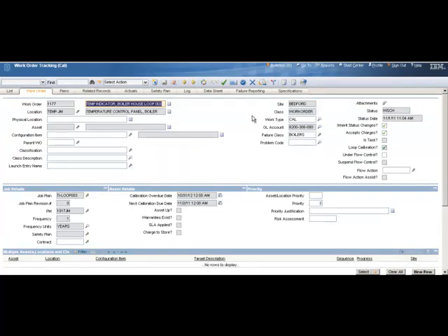I forced it to generate a calibration work order, and I can always tell because it says Cal up here. It's the way it's generated. It's generated in waiting for scheduling status, and that can only be done by generating it from a PM. This is checked off as loop calibration because this is a loop calibration. And I've got my location up here. It's my loop itself. I got temperature control panel boiler is a loop, and I made up a location just for that loop.